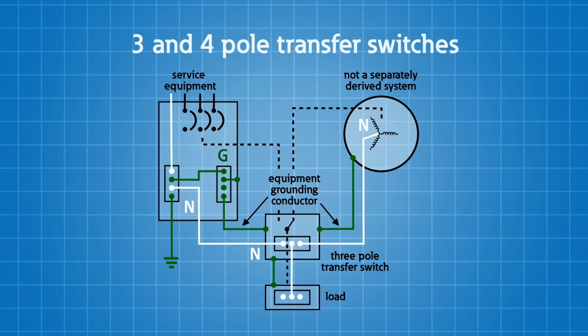Now, sometimes people will drive a ground rod and bond the generator hull or the structure to that ground rod, and that ground rod is supplemental. So it's not required by the National Electrical Code. It is a supplemental type of grounding. A purposeful connection between the neutral, that grounded conductor, and that ground rod system, the grounding system over there on that generator, may occur in the field, either on purpose or by mistake.